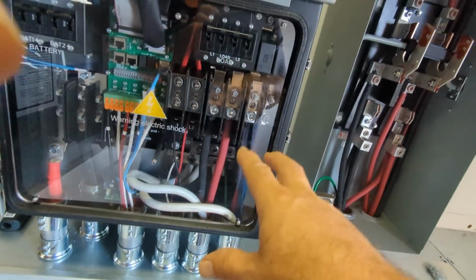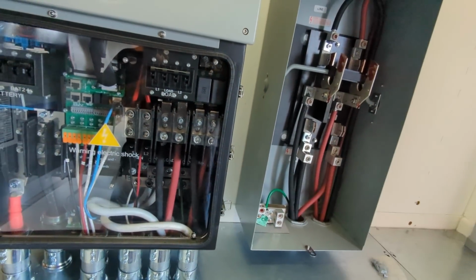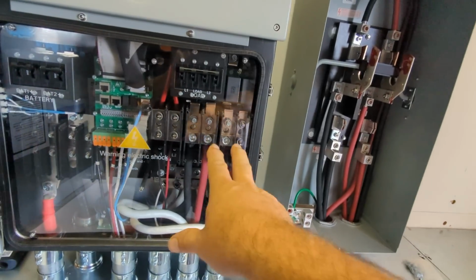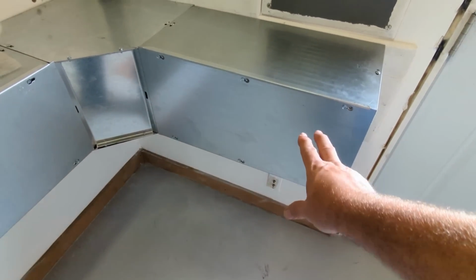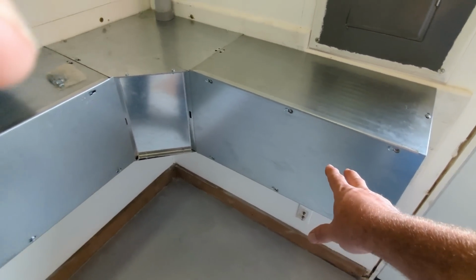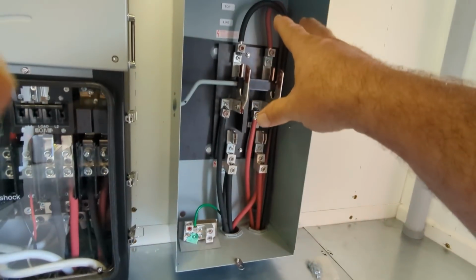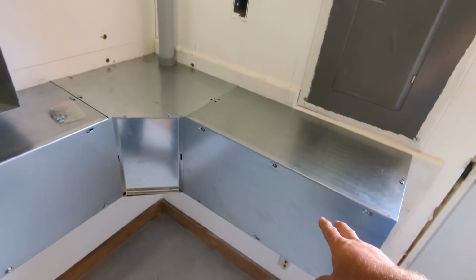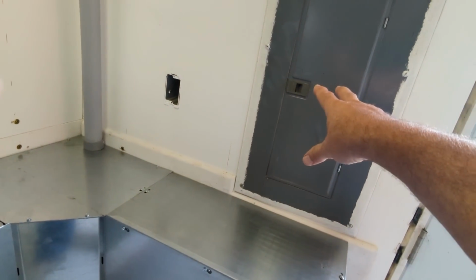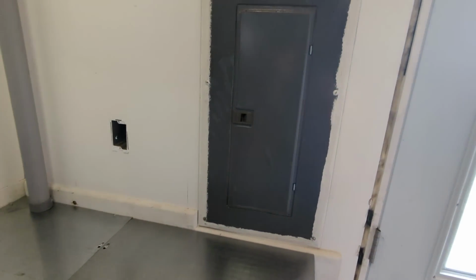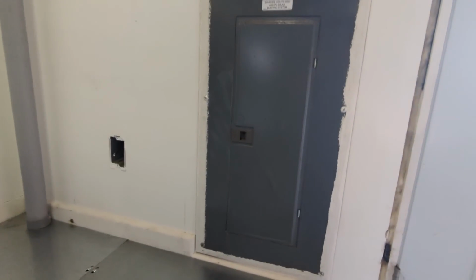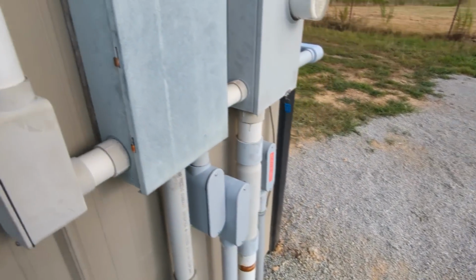Well, on this one, sometimes we just go right to the top of the bypass, but because we're running multiple buildings, we come out of that load and we hit a power distribution block over here. And that power distribution block splits to the bypass, and it also starts to split off to this panel. And then there's an RV park kind of sub panel I'll show you. And also the feeders that he trenched all the way down to his house are landed in that power distribution block. So we're feeding that panel inside.